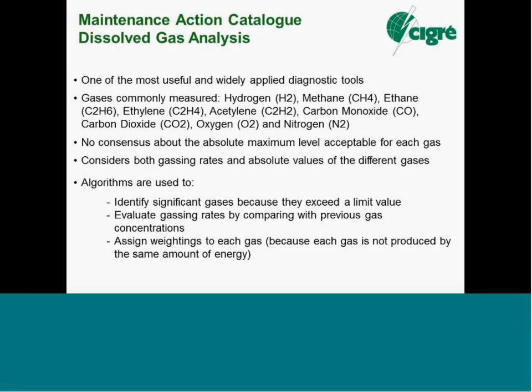There's IEC standards and there's IEEE standards. Both are useful to learn more about getting a better feel for interpreting the relative levels of gases. It's so dependent on the energy of the fault in the transformer. Such a complex thing, the oil molecule. Depending on what temperature the fault is, what energy is involved in the fault, you will see different proportions of the gases, determined solely by the severity and the temperature of the fault. Very interesting.